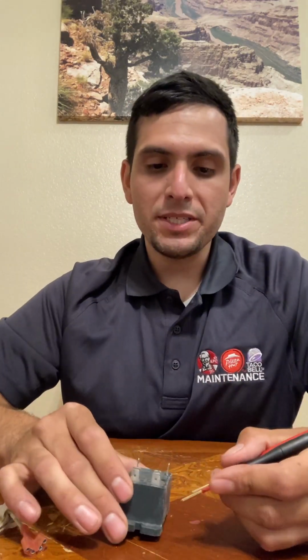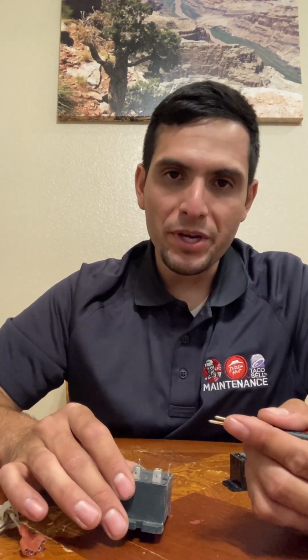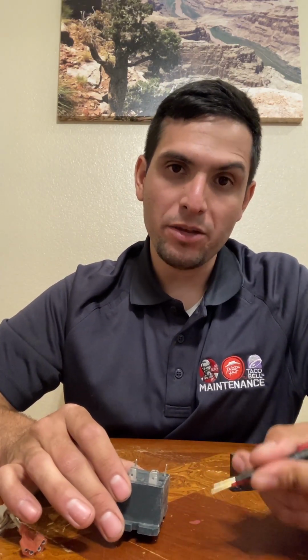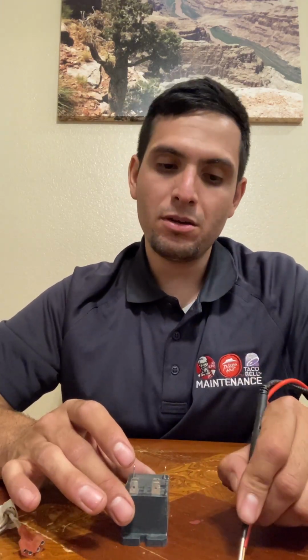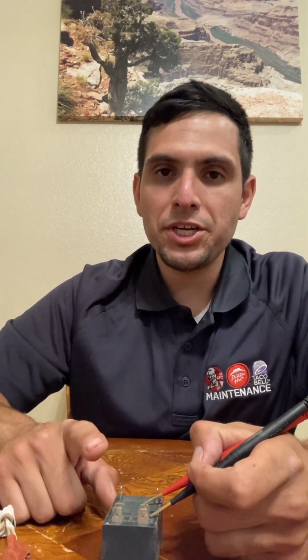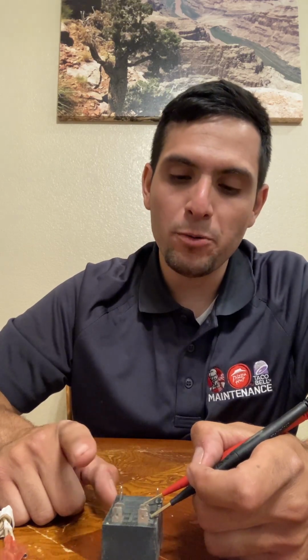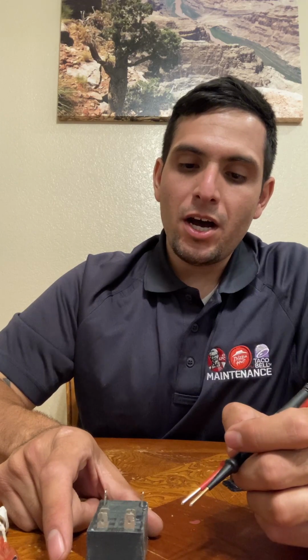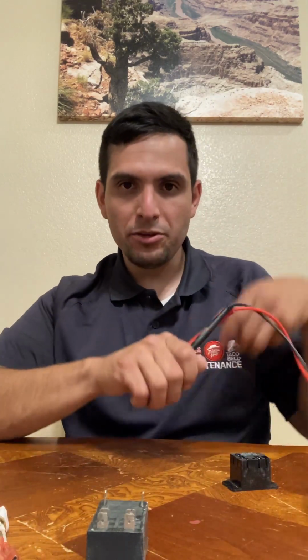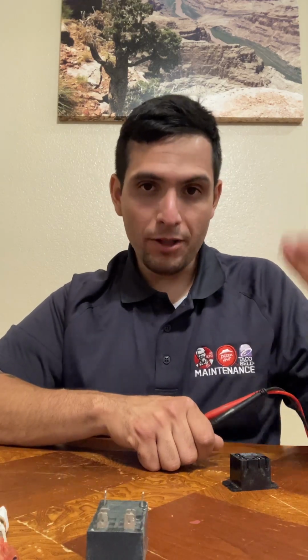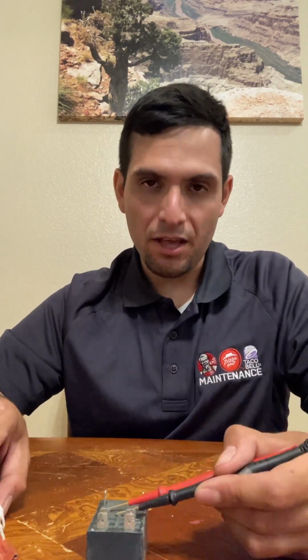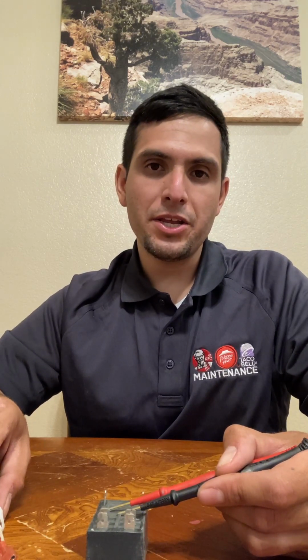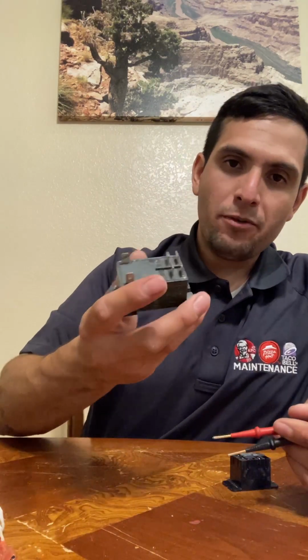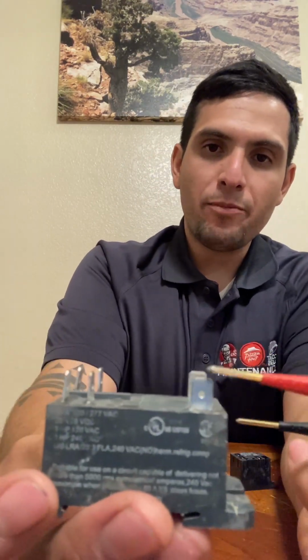And you have to be really careful, because a lot of the work we do, we have to do under live voltage, so we can't check it with the machine off. So obviously, while following all of our safety procedures, you're going to check which relay is the odd one out, just like what we did with the probes. If you have your unit calling for heat, and you can check that by seeing that little dot, or you can see it flashing, then it's calling for heat. So the board's supposed to be telling this relay to call for heat, and then you just check which one isn't getting it. So, for example, normally I don't check my control voltage, but you can.